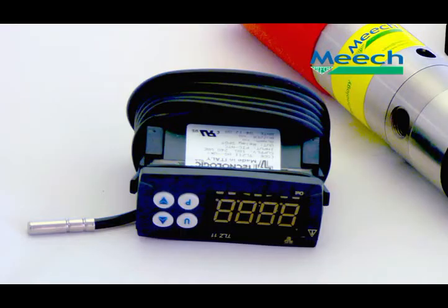For example, if the cabinet cooler overheats when its internal temperature reaches 32 degrees C, the digital thermostat can be set to turn the cabinet cooler on when the internal temperature reaches 29 degrees C and off once it is cooled down to 25 degrees C. This minimises running costs and gives peace of mind the cabinet cooler will not overheat.